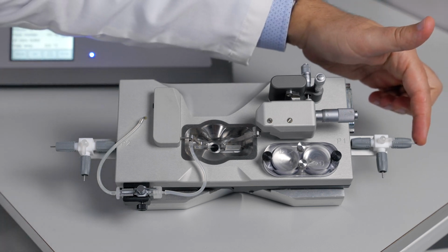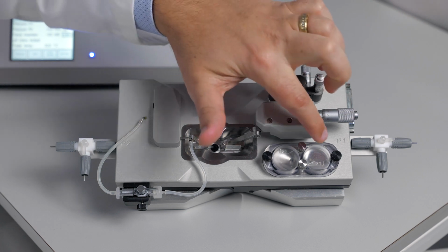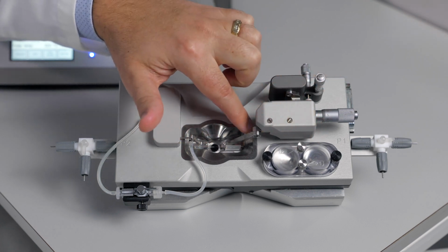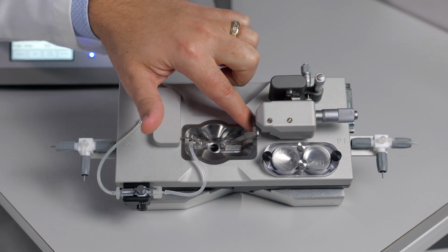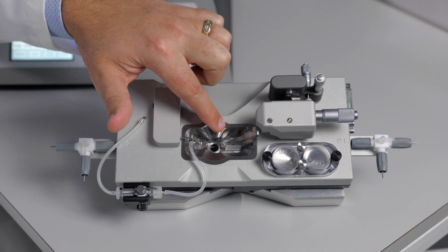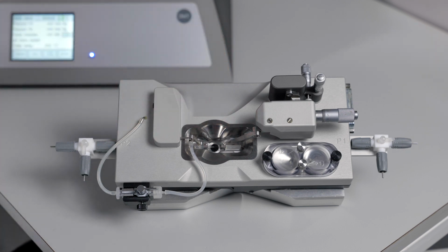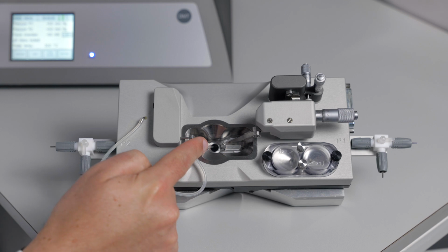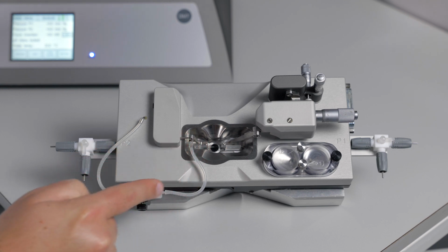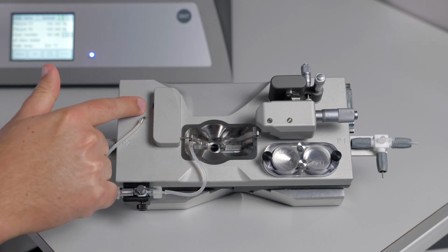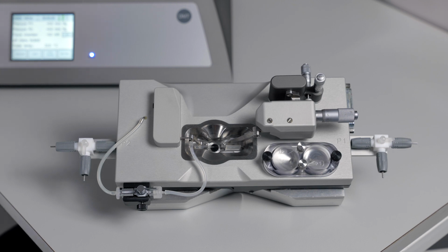Flow will enter the right side three-way valve. It will go through the internal components and through a pressure transducer. It will then enter your tissue chamber, go through the right side cannula and into your vessel. It will then leave the vessel, travel back into the chamber through a second pressure transducer, and then it will return to the interface to close the loop.